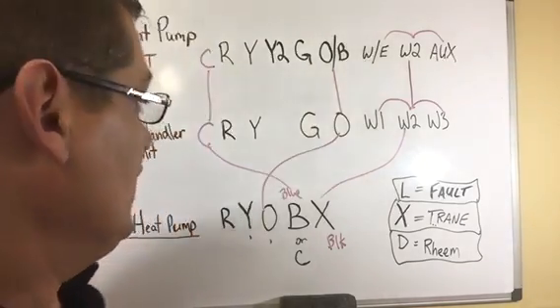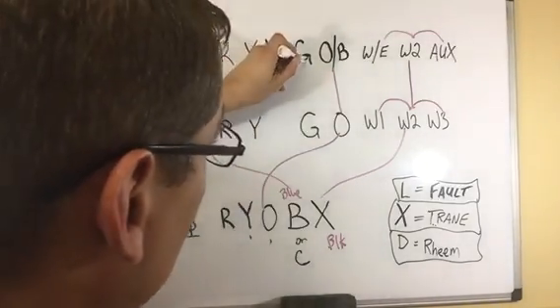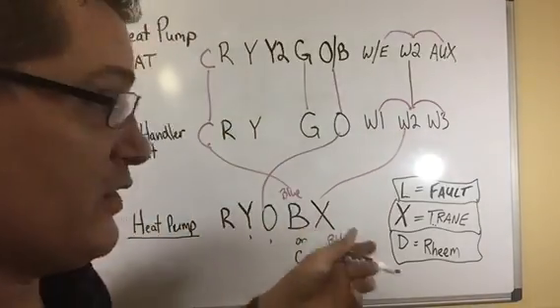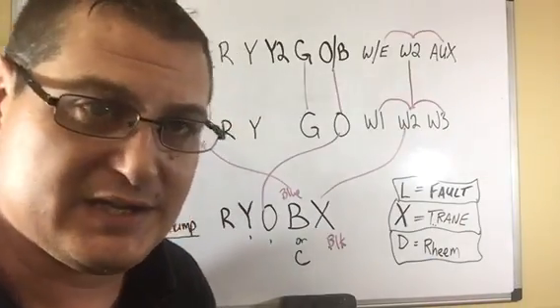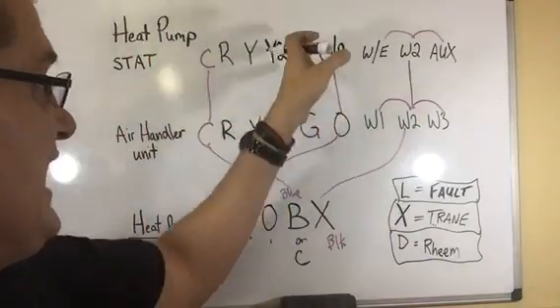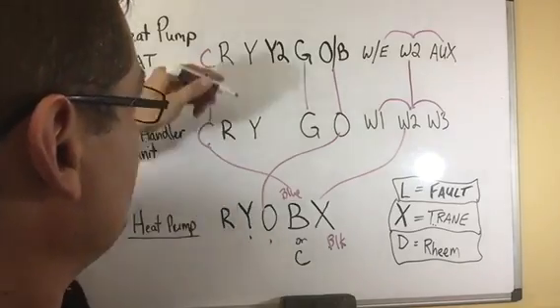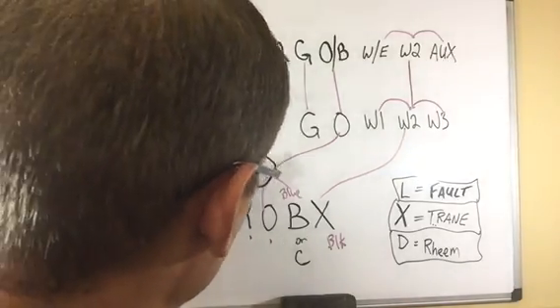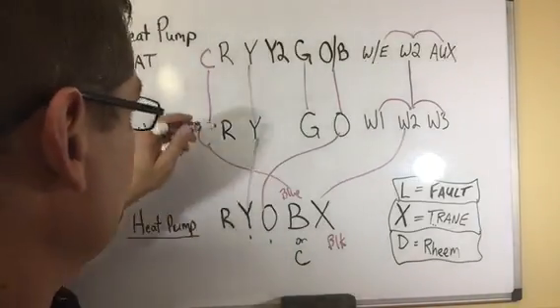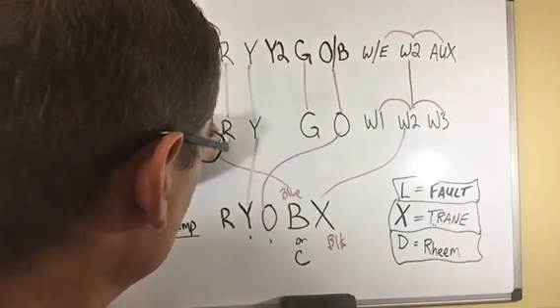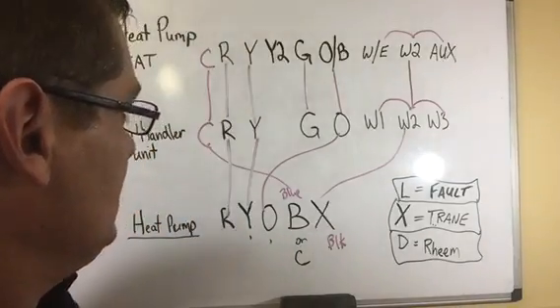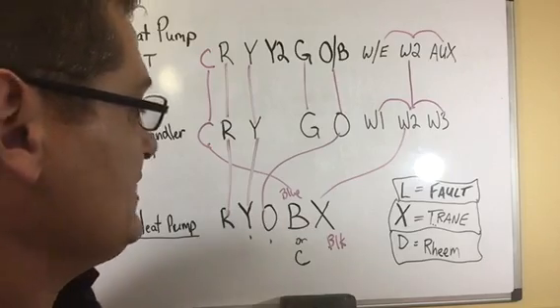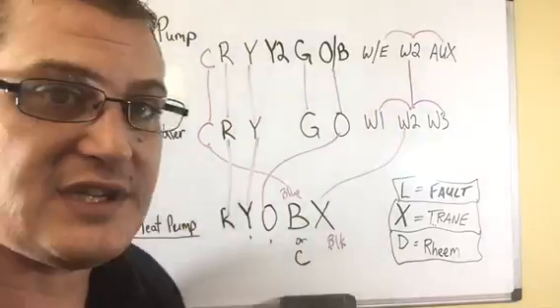G, the outdoor heat pump doesn't require a call for fan, so that only goes between your stat and your air handler. Then you have the compressor, which is Y, and those just all tie together. Then you have your 24 volts. Those all tie together. That's it. That's an entire heat pump system wiring. It's pretty simple.